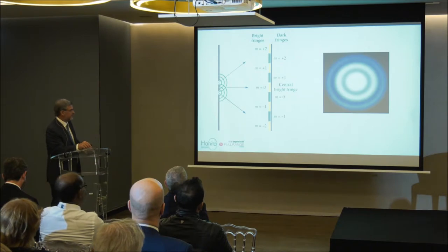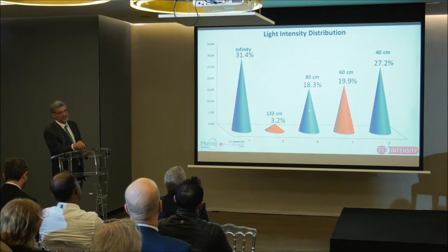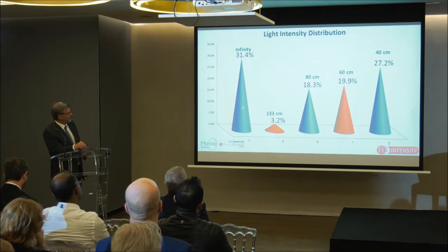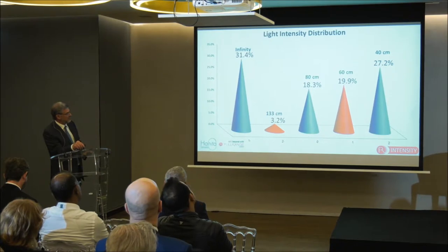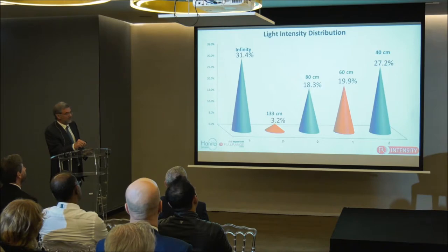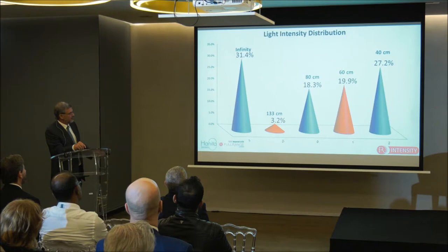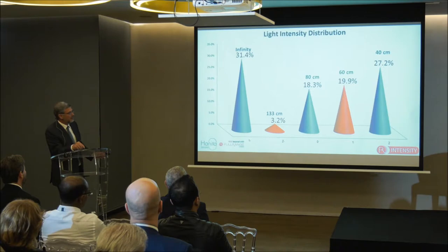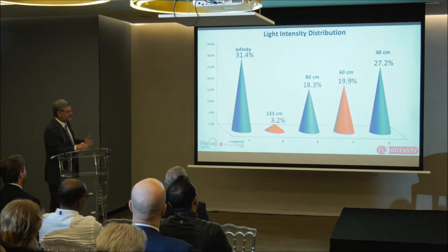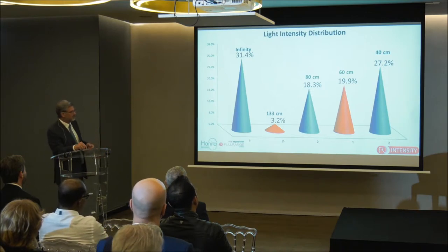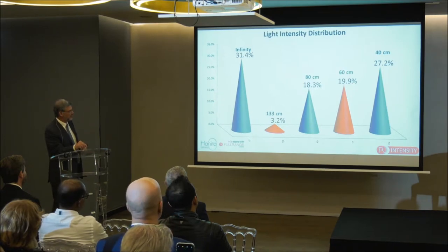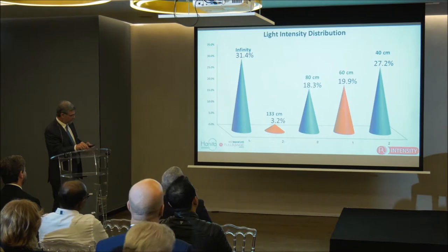In the Intensity lens, the light distribution is rearranged: order zero is assigned to intermediate, while order one goes to far/infinity and another order to near. This means light going to distance is still quite strong and satisfactory. But the most impressive part is the near and intermediate — the light distribution is very effective in this specific lens, with the three foci of far, intermediate, and near, plus the two intensity foci shown here in red.